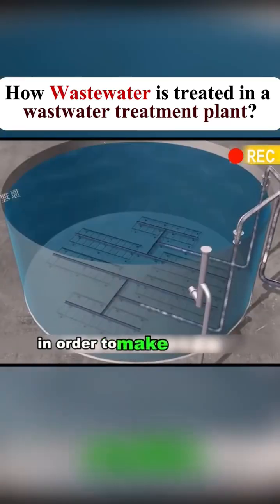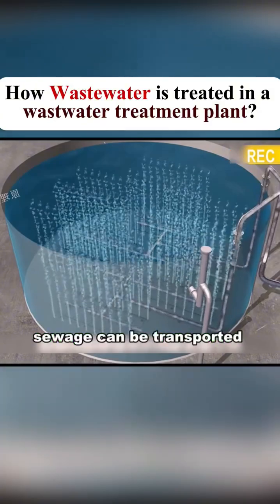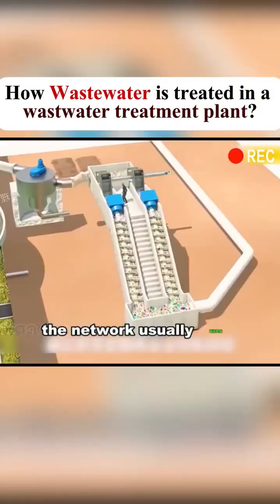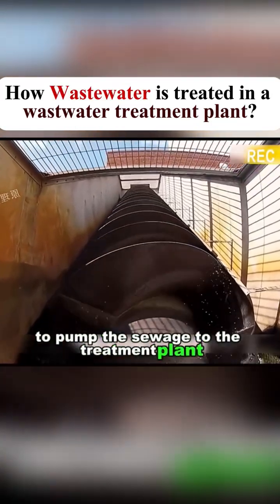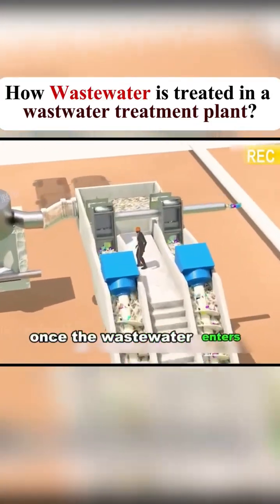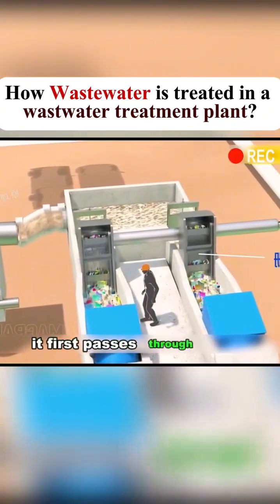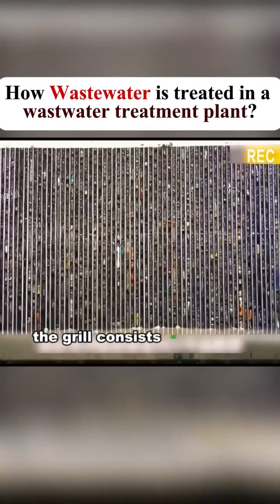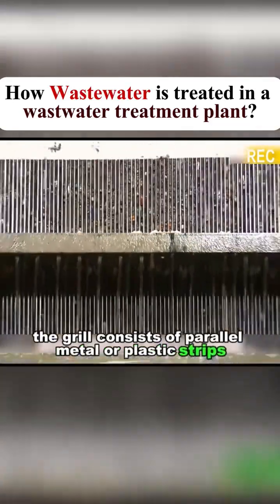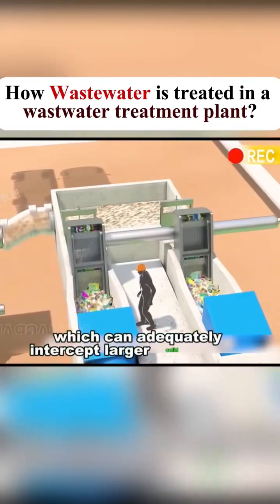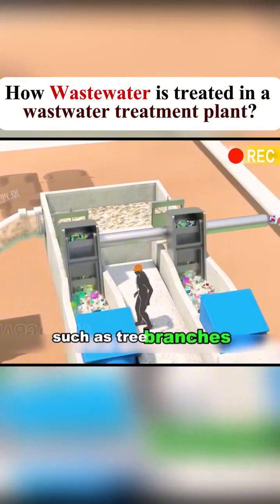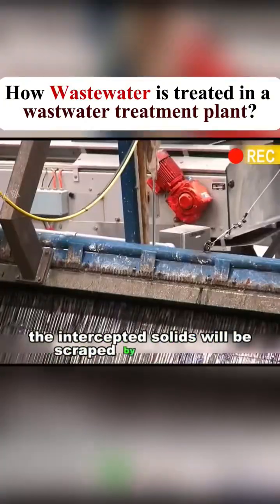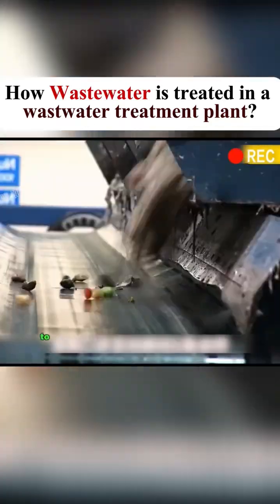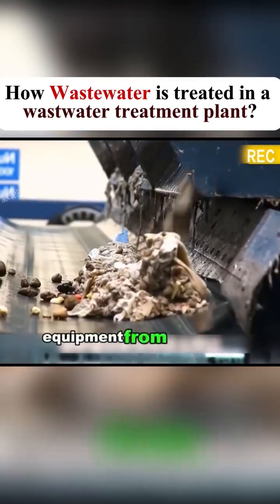In order to make the turbid sewage be transported smoothly, the network usually uses equipment such as screw pumps to pump the sewage to the treatment plant. Once the wastewater enters the treatment plant, it first passes through a grill. The grill consists of parallel metal or plastic strips, which can adequately intercept larger solid wastes, such as tree branches, plastic bags, and stones. The intercepted solids will be scraped by the scraper to a special channel to prevent the subsequent treatment equipment from clogging.